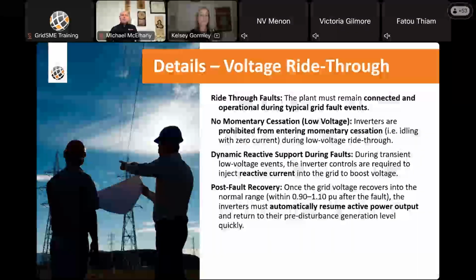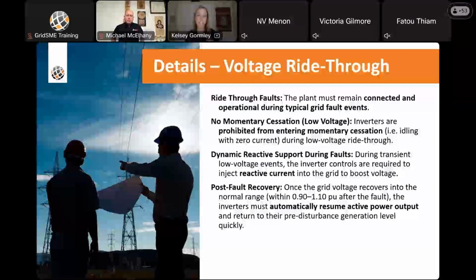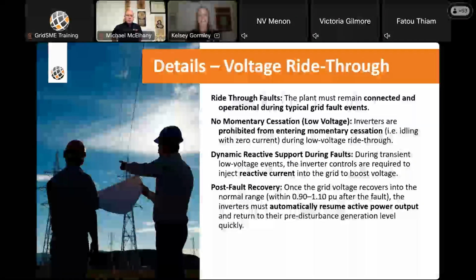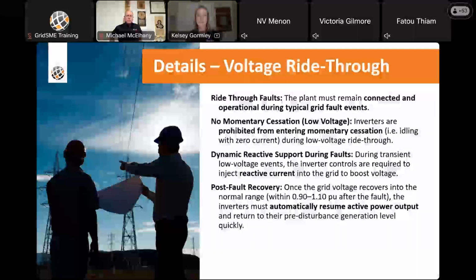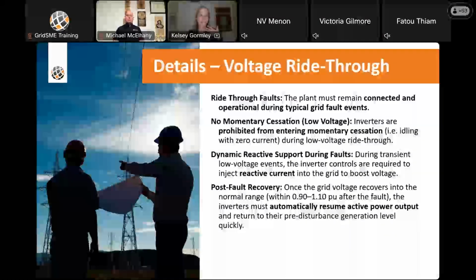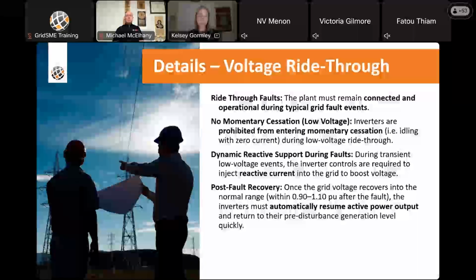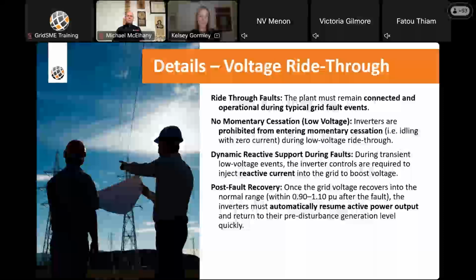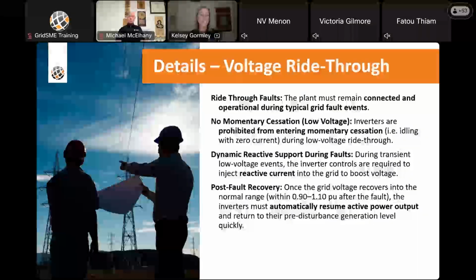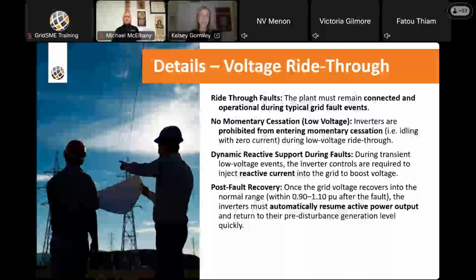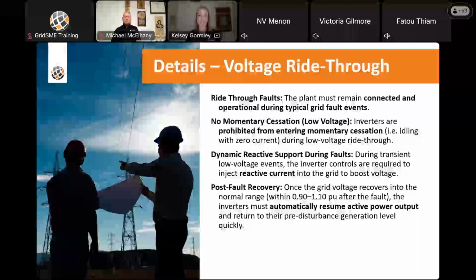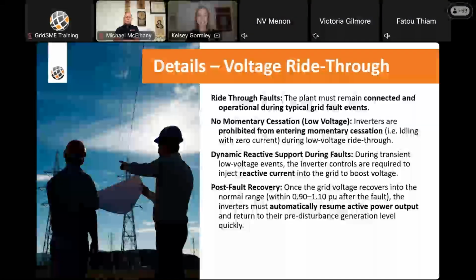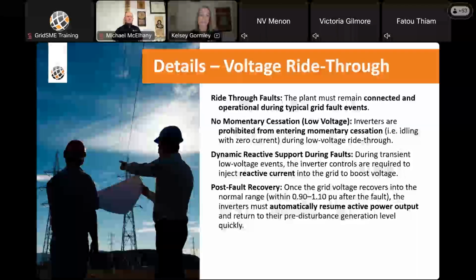The reactive current must be proportional to the voltage drop, delivering full available reactive output when the voltage is 0.5 pu or below. On the other hand, for transient overvoltage conditions, inverters must remain online and absorb reactive power. That means they're producing negative VARs potentially to help bring that voltage back down. This behavior is known as dynamic VAR injection and absorption, is analogous to a traditional generator's exciter response, and is crucial for stabilizing voltage during faults.